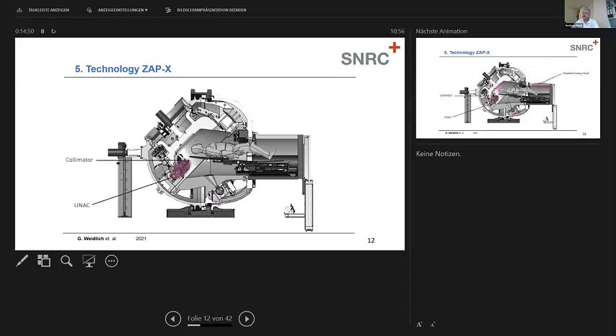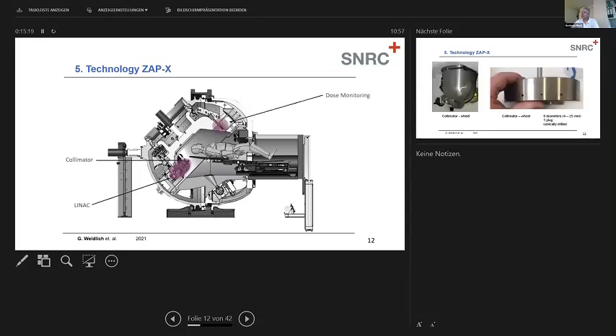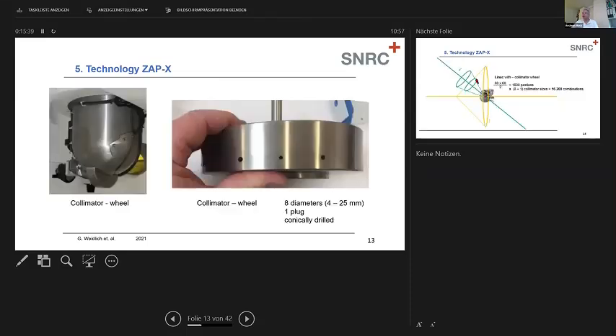Then we have the small standing wave LINAC having a collimator wheel in front made of tungsten with a diameter of 16 centimeters. If you keep in mind that the distance from the source to the unit center point is only 45 centimeters, already 1/3 of the distance is guided by a conically drilled hole in this collimator. We have a real-time dose monitoring system. That means the dose, after being penetrated through the patient, is measured and compared to the dose calculation prior to treatment. So this is a collimator wheel, which you see.